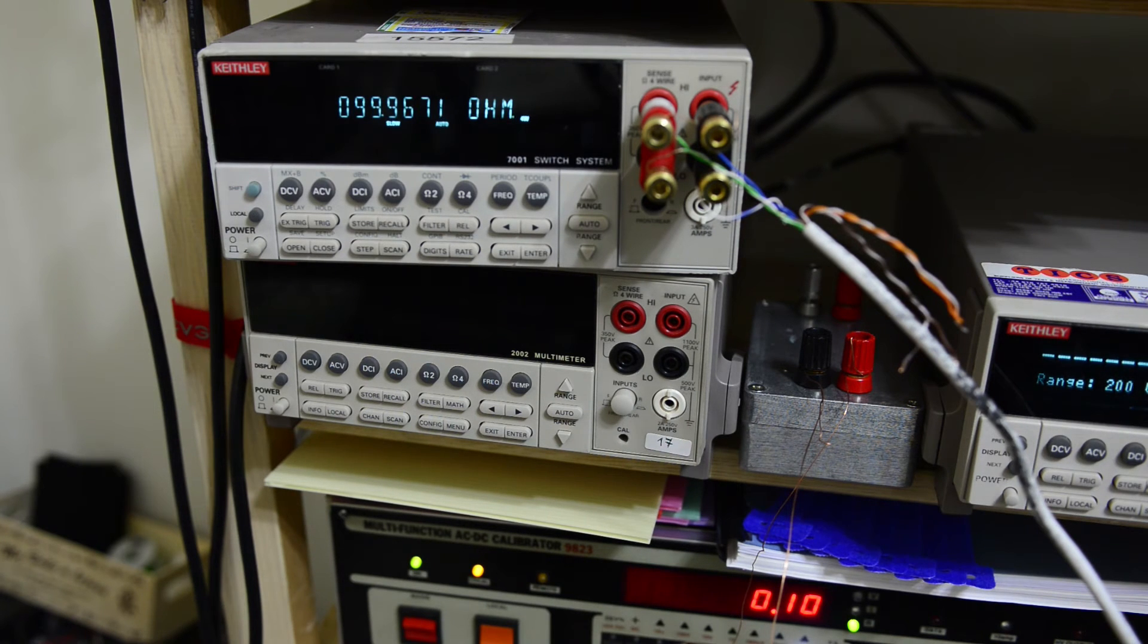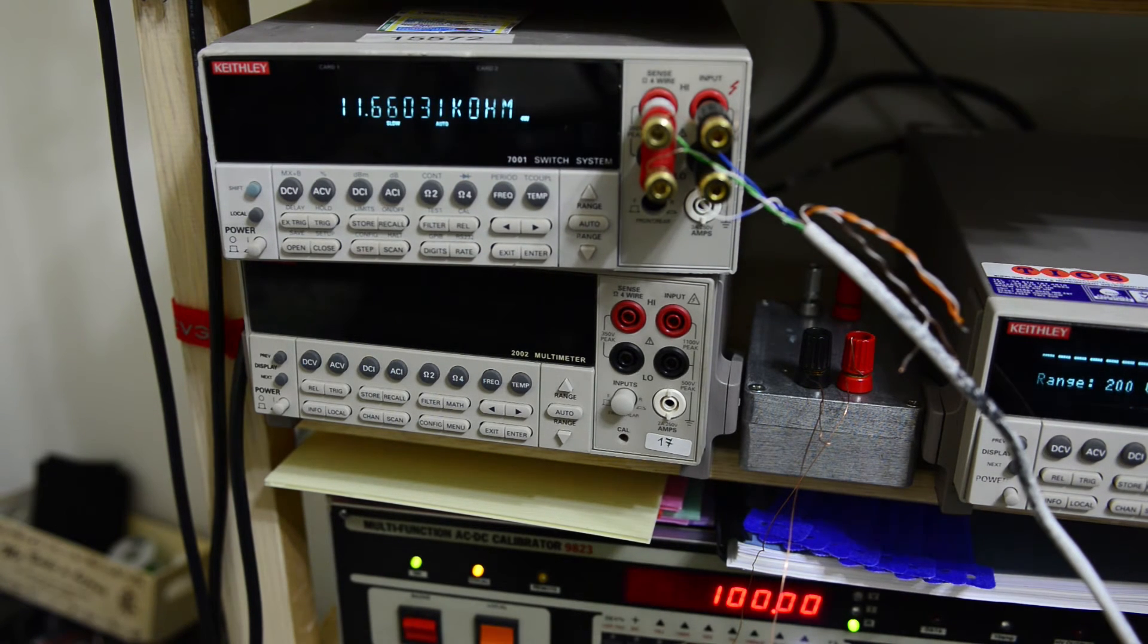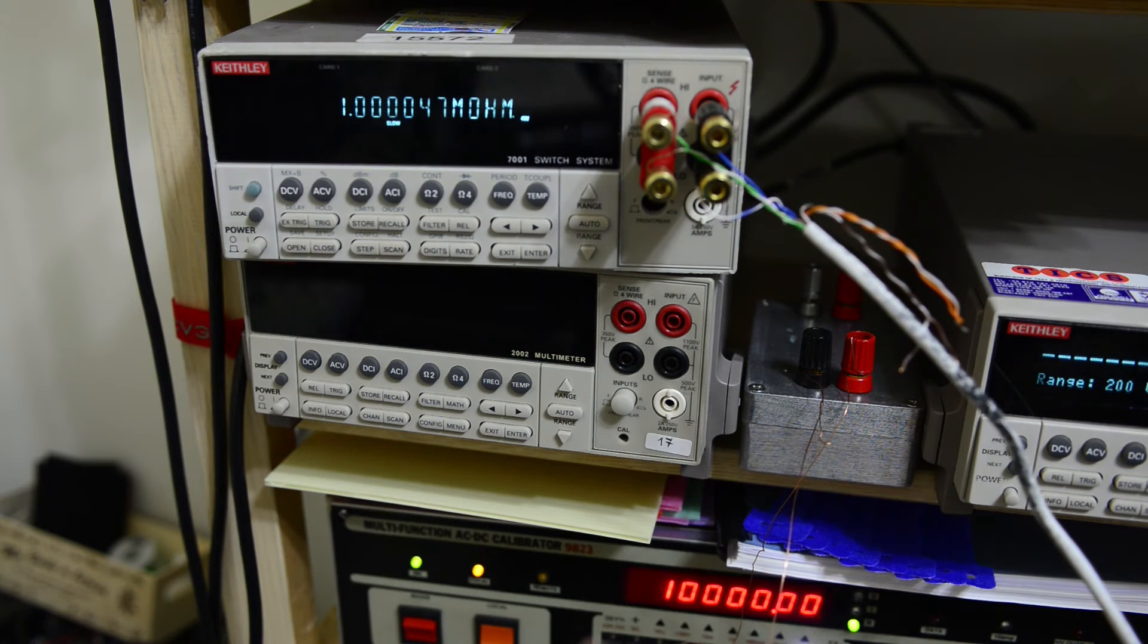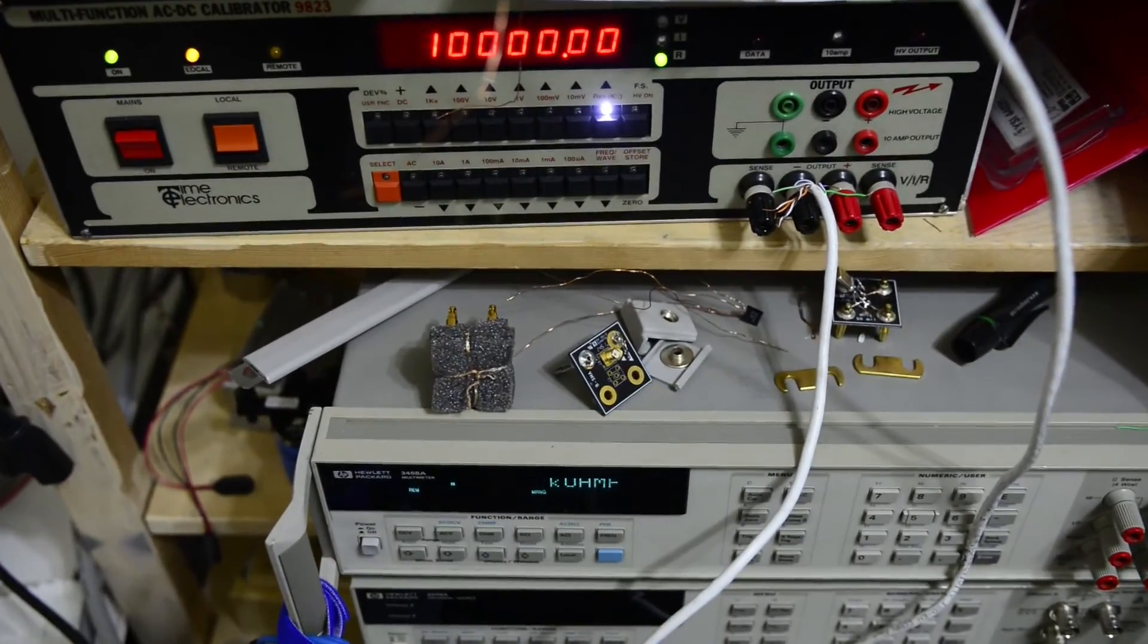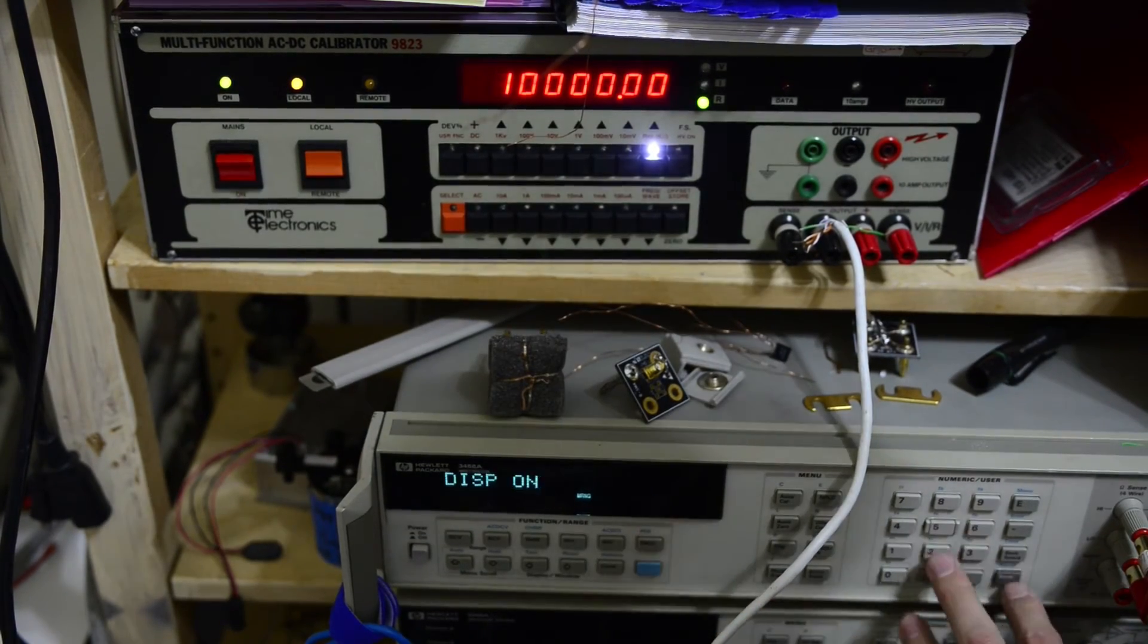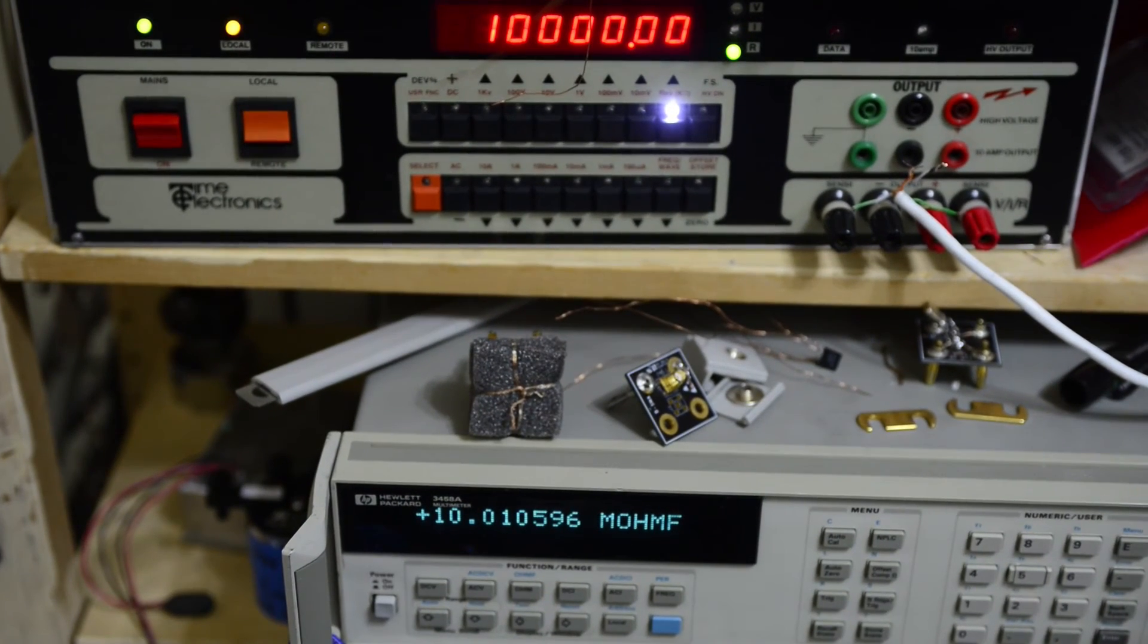Now take a look at resistance measurements and these are using four wire terminal connection. So I'll have to take readings first with Keithley DMM and then reconnect back to HP for crosscheck. I changed my camera position and will use HP meter to read the same resistors.